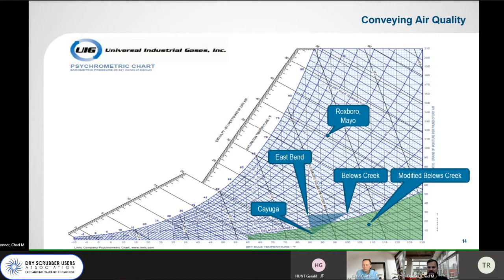And again, that's relatively speaking the amount of pluggage that we saw. Then you'll see the Roxboro, Mayo point up there. They have no air controls at all, and that was the site that had, if you remember a couple slides back, the pallet of elbows. Their solution to scaling and pluggage was to just recycle and clean elbows as they plugged up. They would run less than 2 weeks before they had to swap out elbows.